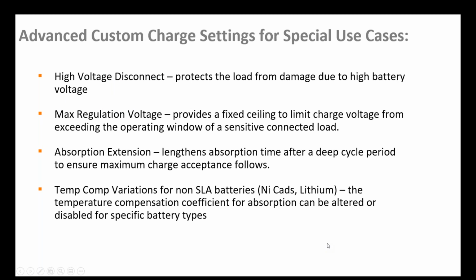Oops, sorry, I think the slides were advancing there. And so you can do that very easily, and again provide that extra security and peace of mind for the sensitive load equipment. We also have a max regulation voltage specification that would provide an added redundancy to make sure that the output voltage to the battery never goes higher than a certain ceiling limit. Even if you had temperature compensation enabled, it would never let it go above that threshold. So that's a useful thing for peace of mind as well.